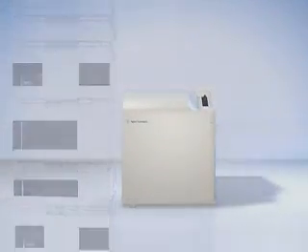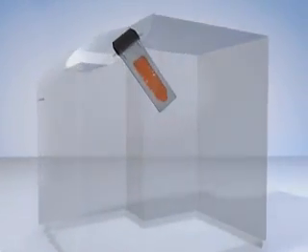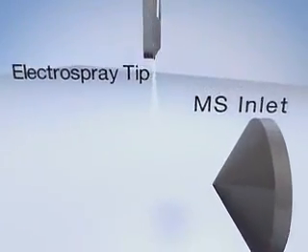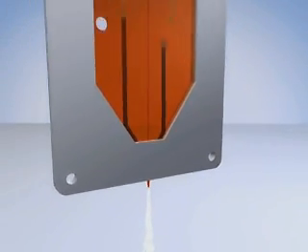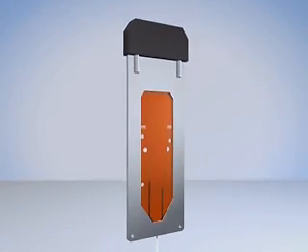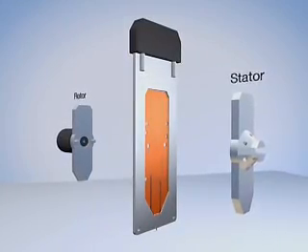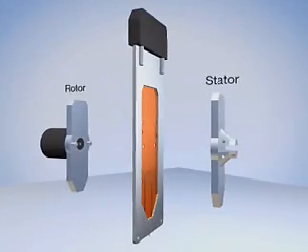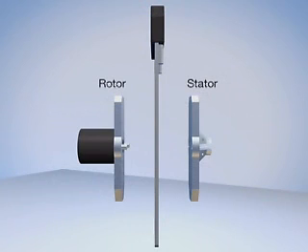The HPLC chip loading mechanism precisely and automatically positions the electro spray tip orthogonal to the MS inlet for maximum sensitivity and robustness, day in, day out. With the Agilent nano-LC, micro-well plate auto sampler and loading pump directly connected to the HPLC Chip Cube-MS interface, an HPLC chip is loaded and leak-tight fluid connections are automatically established by sandwiching the chip between the rotor and stator of the built-in multi-port micro-valve.